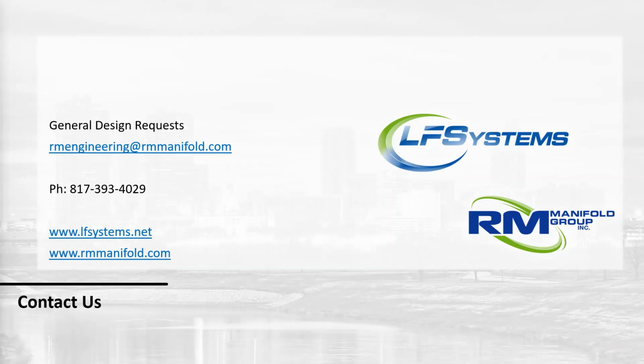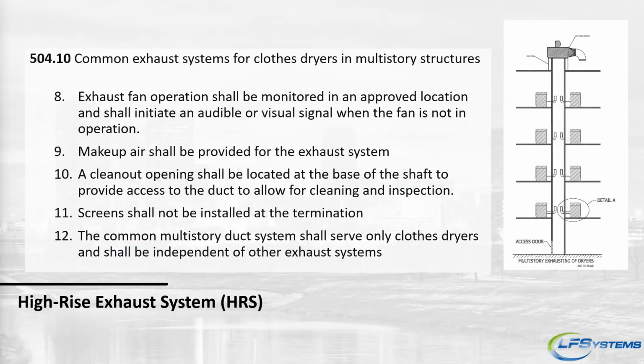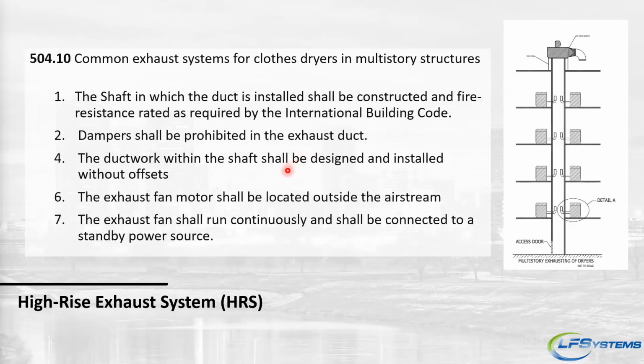I can see if I can pull up where it states that in the code. Yeah, that'd be 504.10. This is for dryers. Again, there's a similar comment on... let me look for it real quick. Yeah, there we go, number 7. So 504.10 does require it, and it has to do with controlling smoke in a fire event. Because if this apartment were to be on fire, yes, the subduct method should prevent most of that, but they want that fan to become a draw point to get the smoke out rather than just lingering in that shaft. So that's the primary reason that I've been told with regards to that code.